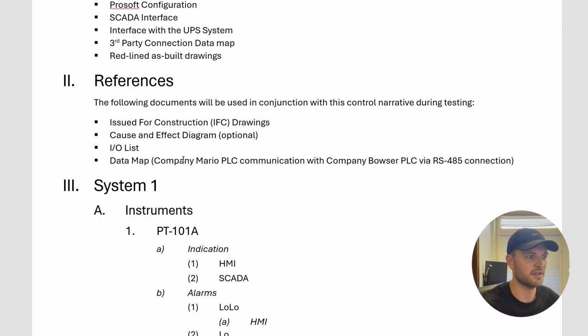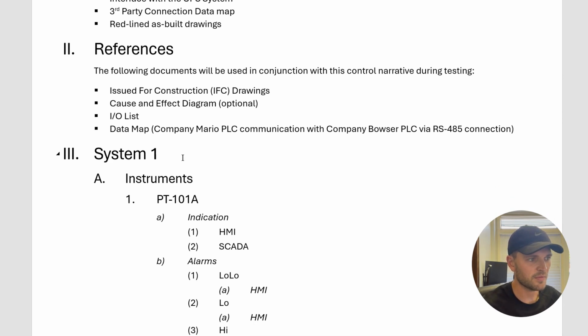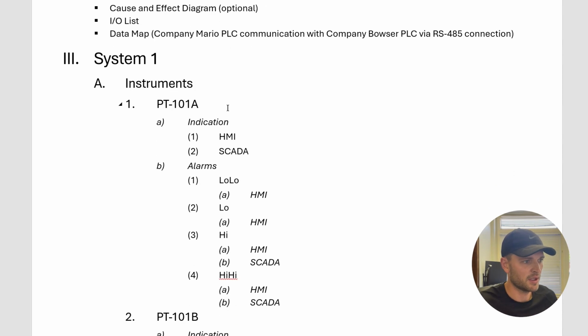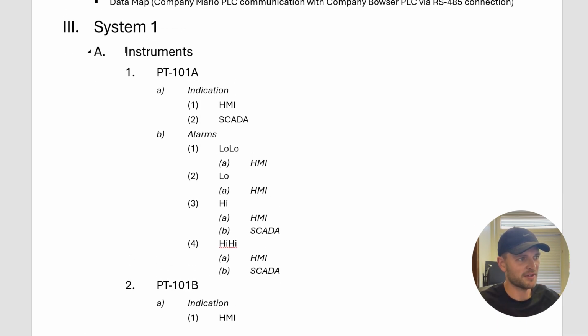The next section is references. In this section, we just outline the documents that will assist in the testing. Like I said earlier, as an engineer, I love the control narrative because it just funnels right into my checkout and testing document. So I don't have to recreate any sort of documents or spreadsheets or anything like that. We have IFC drawings, cause and effects diagrams, which are optional. And I put optional, and I'll dive into why here in a second. IO lists, just for checking the physical IO, and then any data maps that you might have for communicating from PLC to PLC or maybe PLC to another device. Okay, if we dive in a little more, I break my systems into three sections.